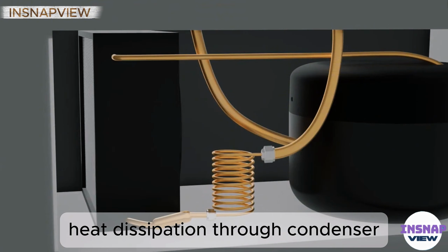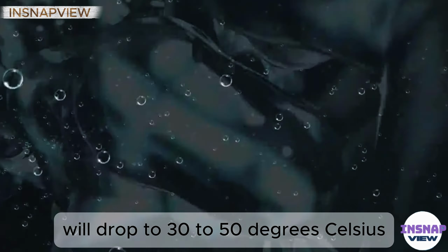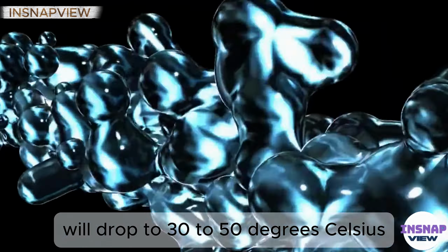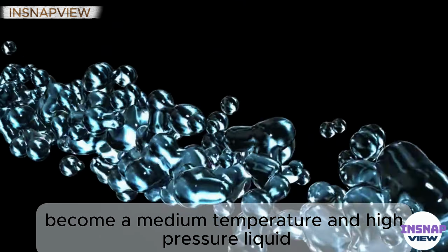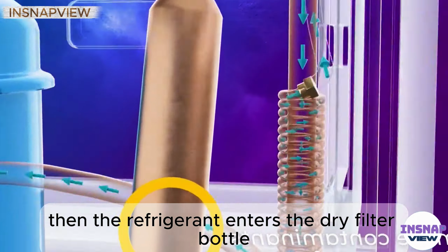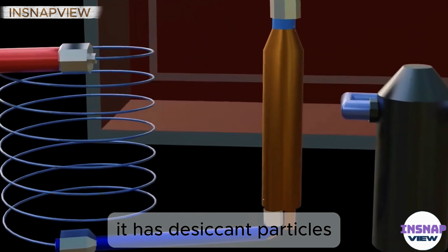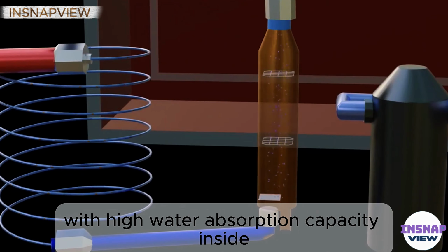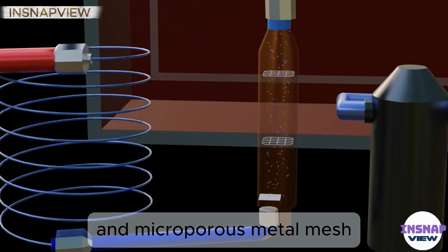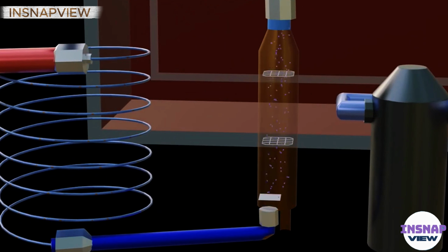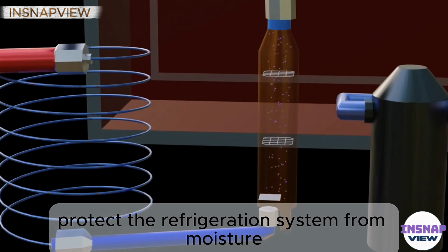Through heat dissipation in the condenser, the temperature of the refrigerant will drop to 30 to 50 degrees Celsius, becoming a medium-temperature, high-pressure liquid. Then the refrigerant enters the dry filter bottle. It has desiccant particles with high water absorption capacity inside, and microporous metal mesh or ceramic filter elements protect the refrigeration system from moisture and impurities.